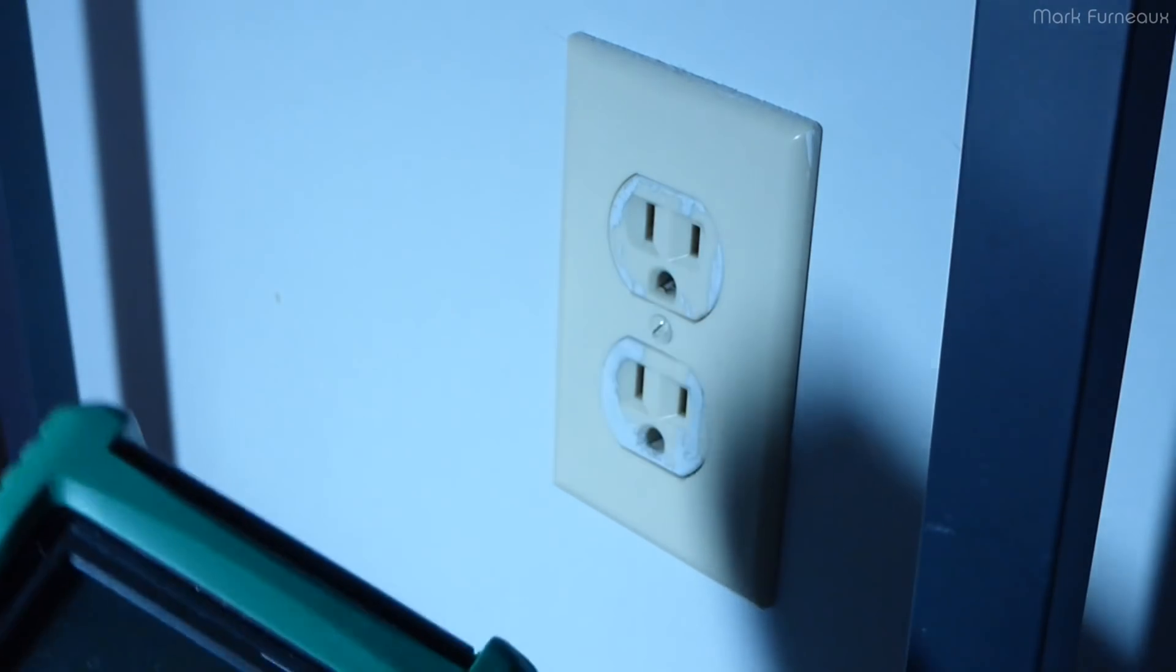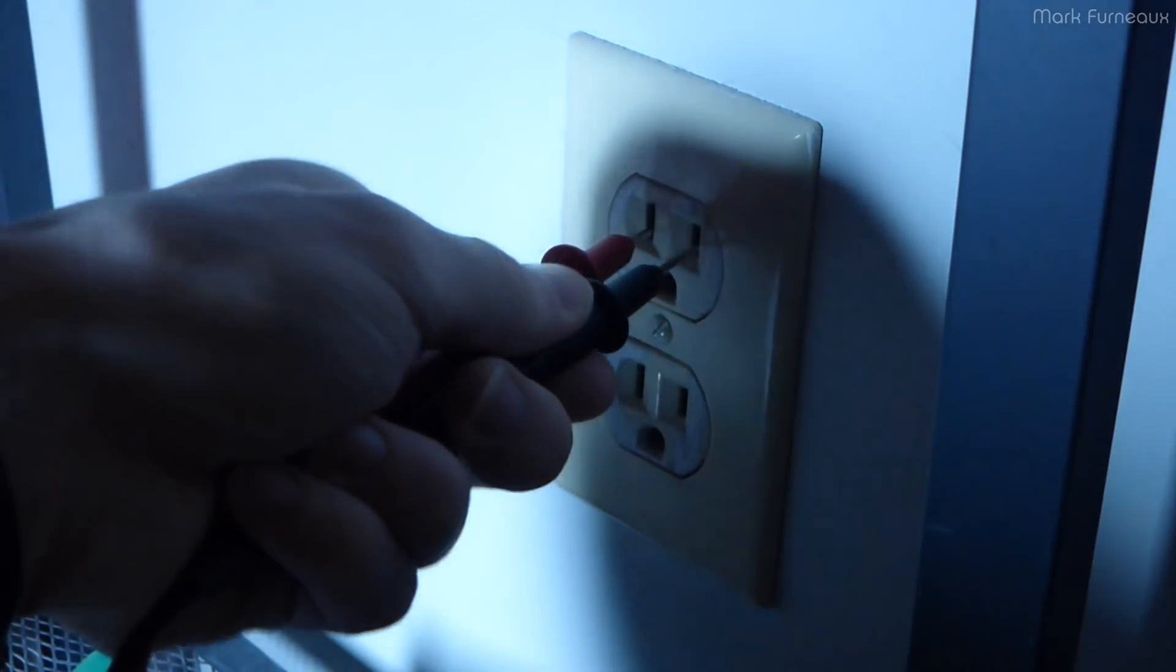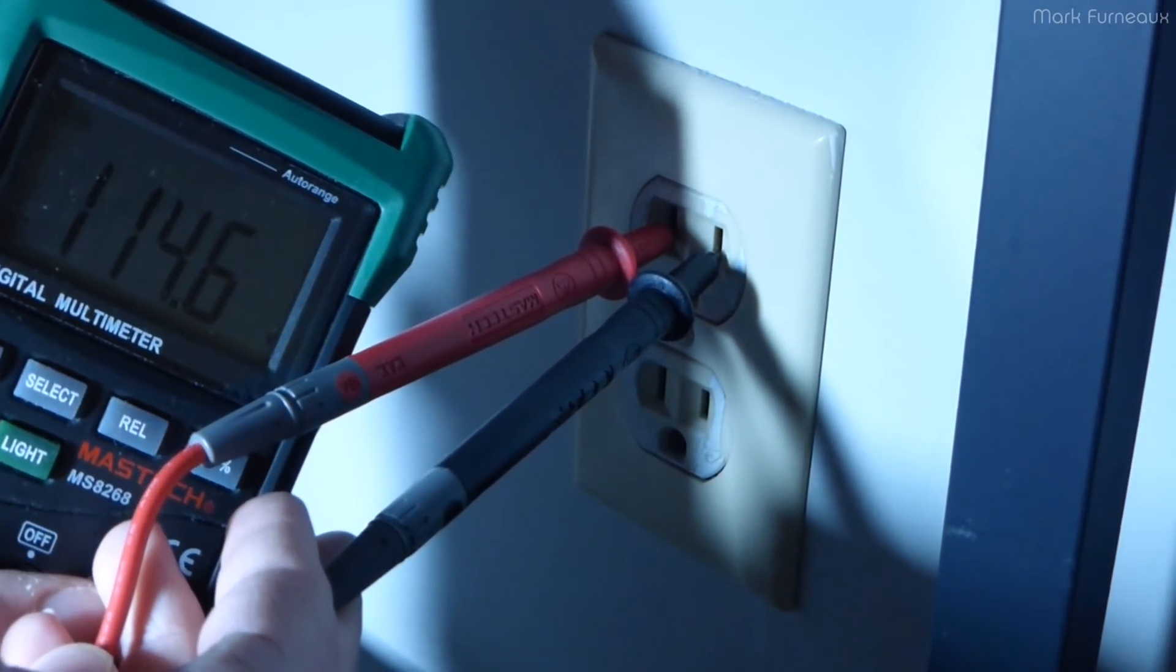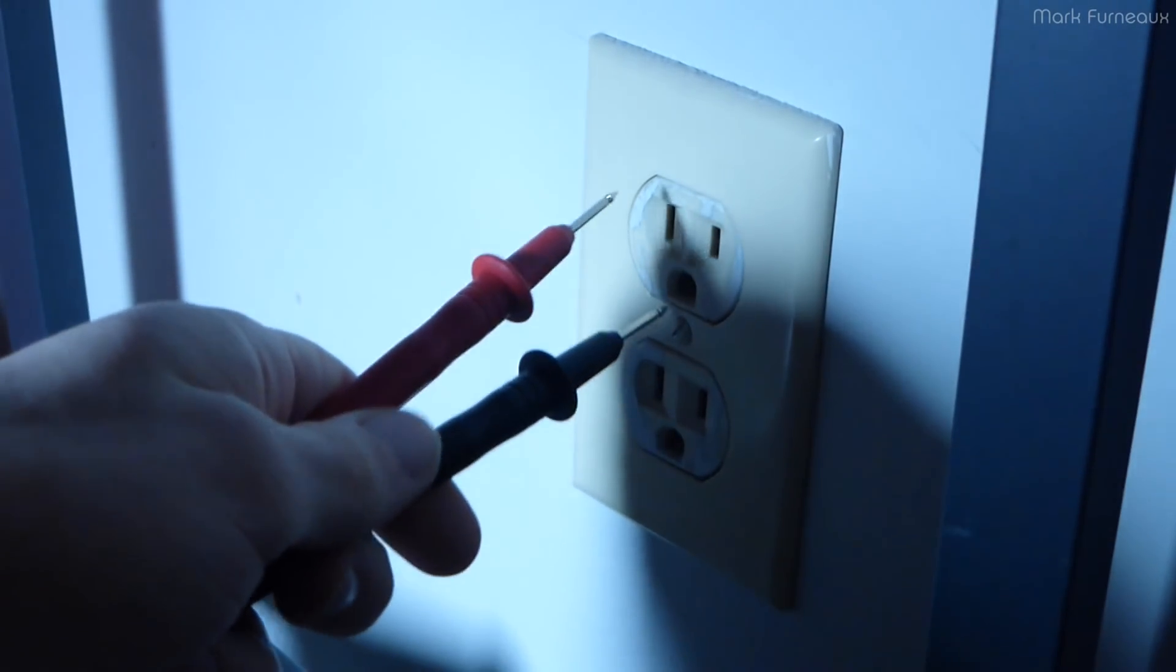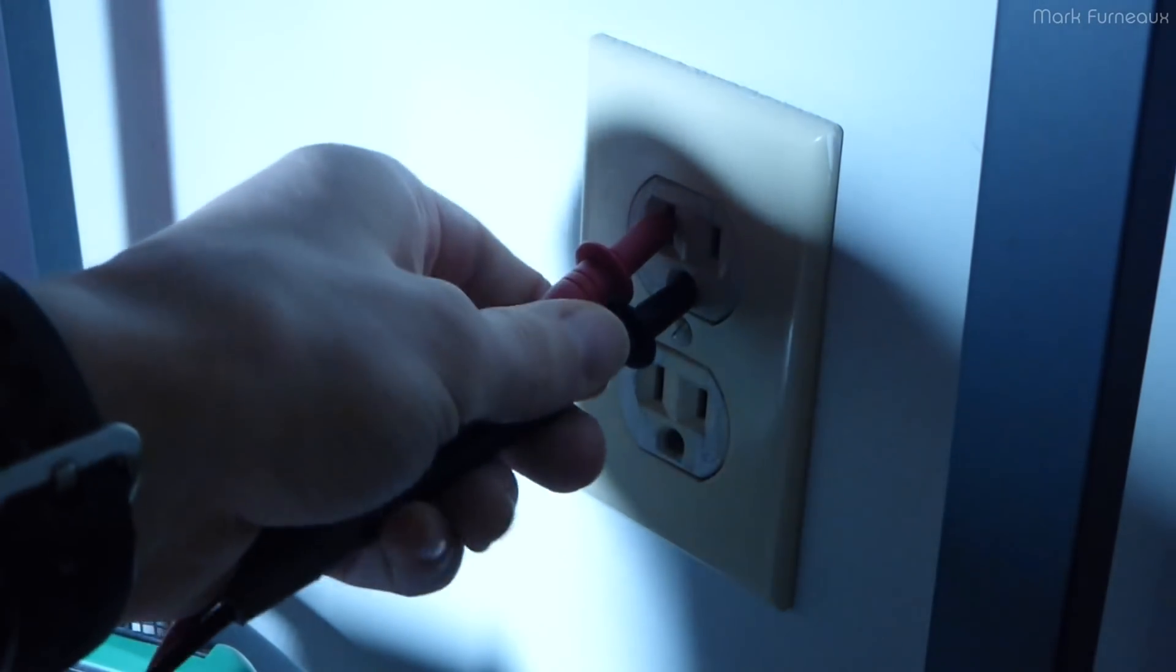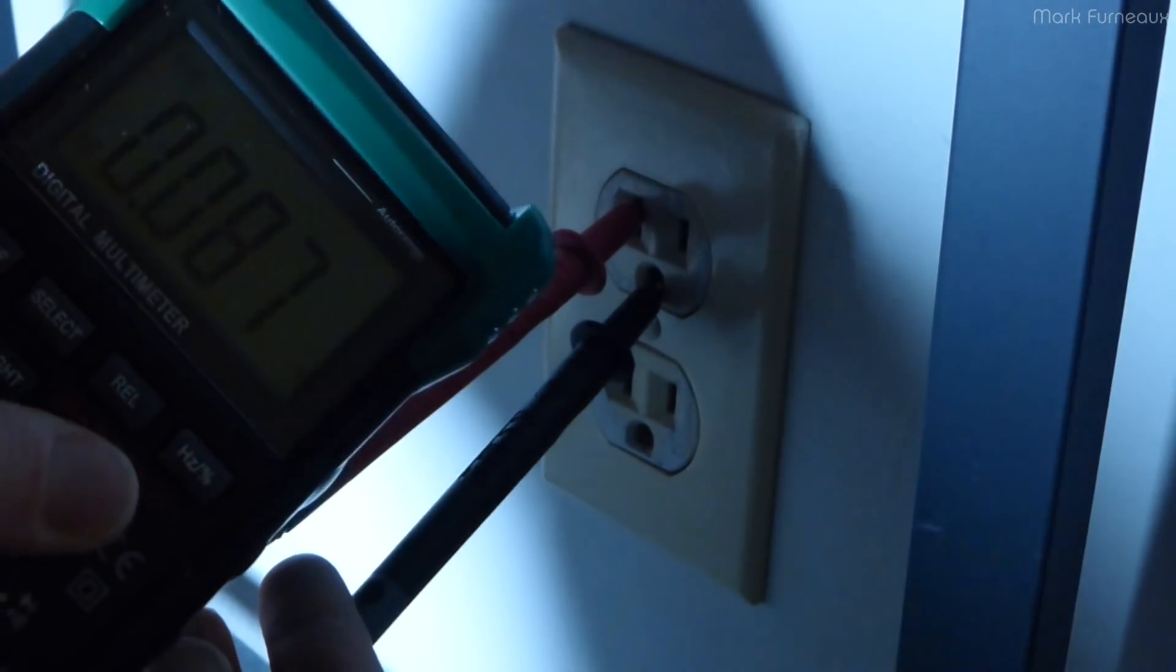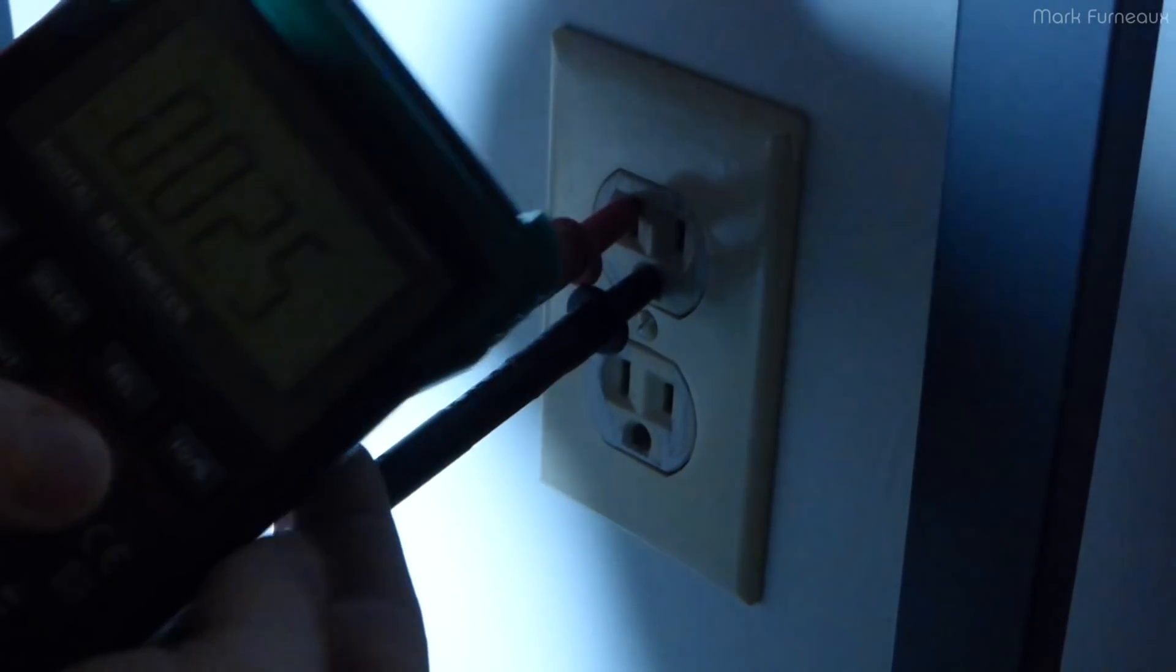So if you take your multimeter and you put it on AC volts, and we connect between the neutral and the live, we should see mains voltage. In my case it's 114.6, which is what we would expect. Now if we check between ground and neutral, we expect to see a voltage that is incredibly low, because of course these two are tied together at some point in the mains wiring.